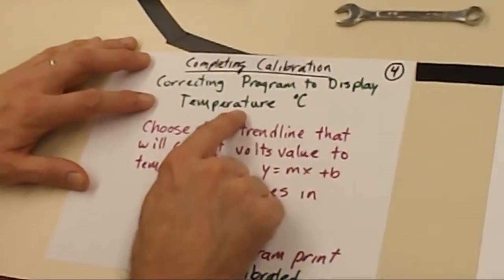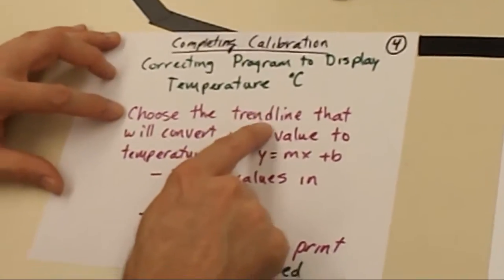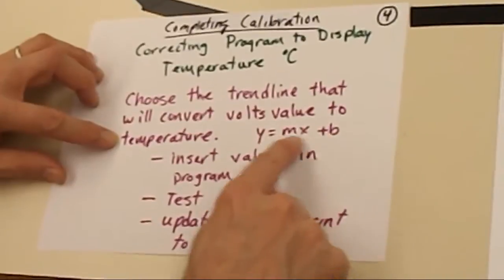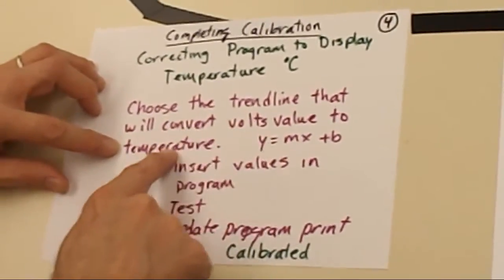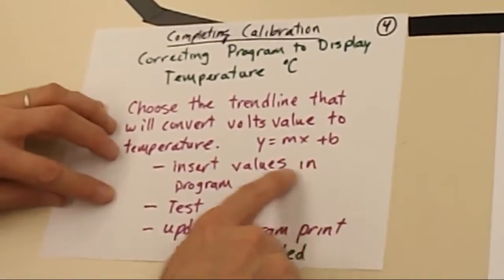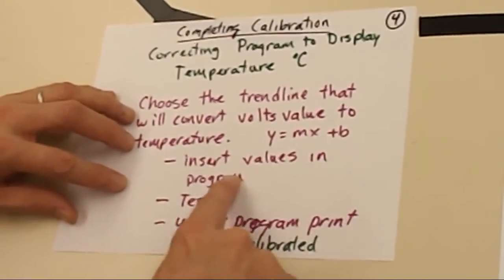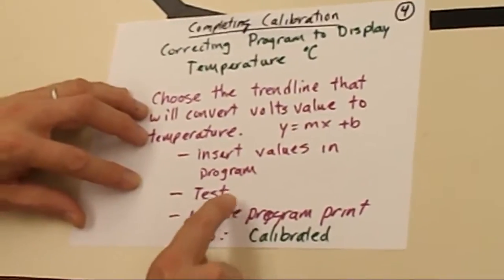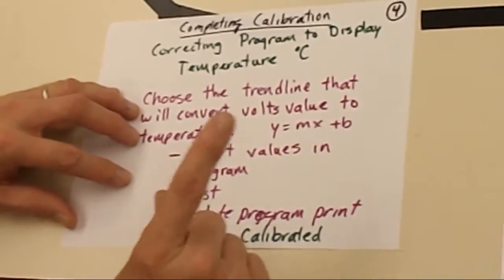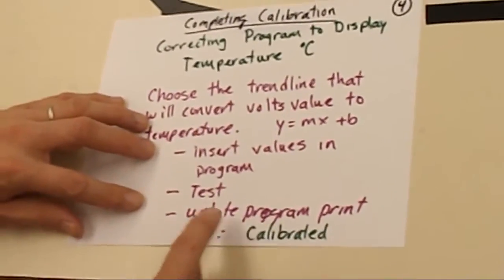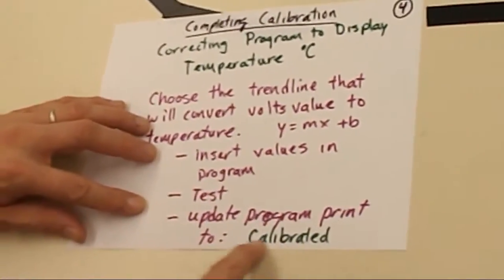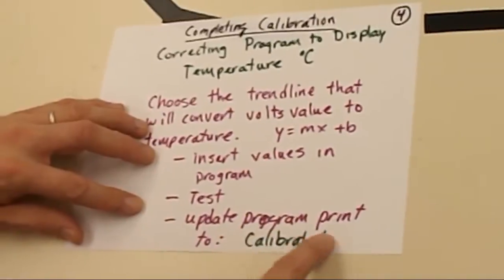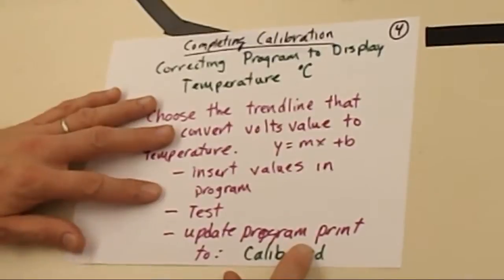So basically, we're going to correct the program to display the temperature in degrees C. What you have to do is choose which trend line that will convert the voltage value that it's read into temperature. So from your two graphs, you select that equation from the trend line that allows you to convert voltage into temperature. So we're going to select the slope and the y-intercept values, and we're going to insert them in the program. If you read the program carefully, you can see where there's a conversion formula. So use your values, insert them, rerun the program, verify it and load it, and then test it out and see how close your program reads to the actual temperature on a couple of your samples. Once that's correct and it looks like it's working properly, update the program to actually say that it's a calibrated value.